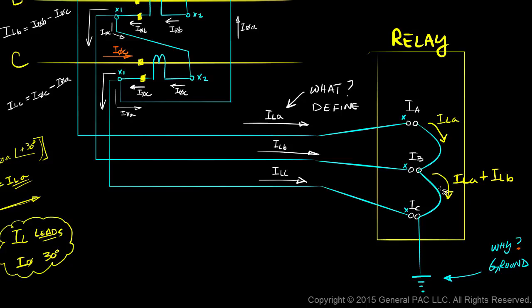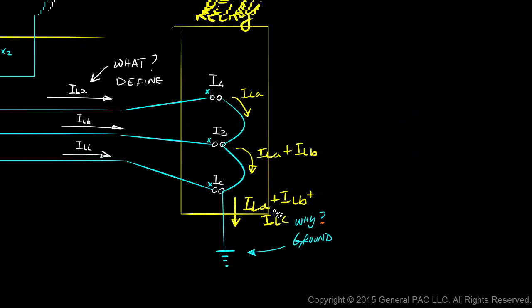Which makes sense, right? Line current b is flowing into the polarity side here. Line current a is flowing into the non-polarity side there. And what's flowing out is the sum of what's flowing in. And lastly, what's flowing to ground is line current a plus line current b plus line current c. Let's move it over here.